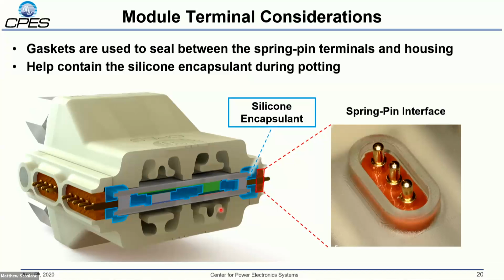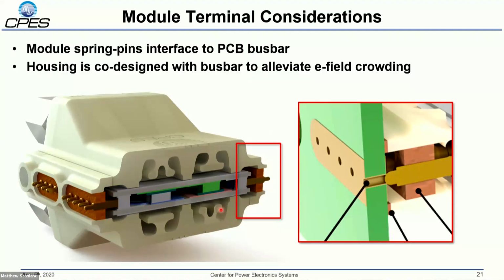This terminal has been designed with spring pins so it can interface directly to a PCB bus bar. This exploded view shows the spring pin passing through the water jet gasket and interfacing into a PCB bus bar. We actually use the housing and the PCB bus bar to fully enclose this terminal and break any in-air paths between terminals or between the terminals and other metal components in the system.